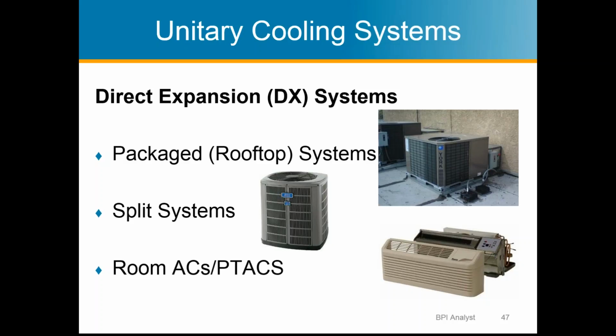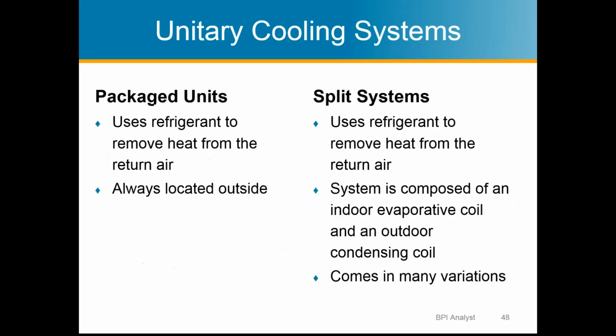But it can also have heating elements in it, so it can either be heated electrically by electric resistance, or it could be a heat pump PTAC. So sometimes you'll see PTHP, package terminal heat pump, and then if you've got a heat pump, you're doing heating and cooling both in the same system. So package units are using refrigerant. Typically, it's possible, though pretty unlikely, to have electric resistance as the principal heating source. Most of the time it uses refrigerant to cool and heat if it's a heat pump. And they're always going to be located outside the house, either on the ground or on the roof.